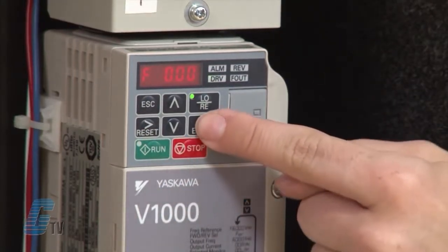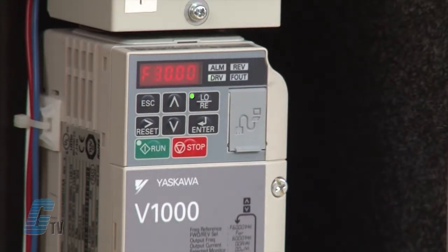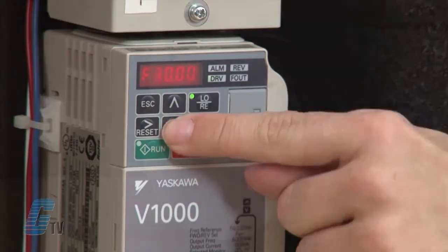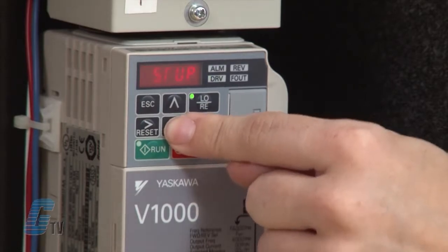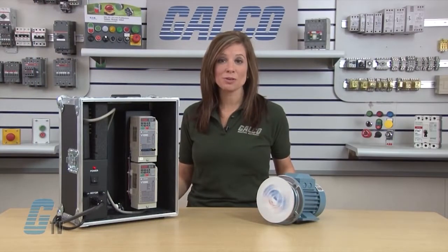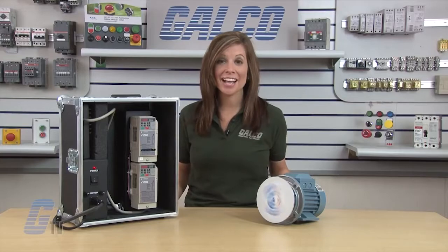Now I can run my drive. If I hit enter, I can manually control my speed. I'll put in 30 hertz. As my drive is running, the display here is still blinking, letting me know that the drive is in setup mode. I can manually adjust the speed with the arrow keys. To get out of setup mode, I will hit escape. I can check my current settings using the arrow keys. This completes the basic auto-tune demonstration on the Yaskawa V1000. The Yaskawa V1000 AC drive, along with thousands of other products and services, are available at galco.com.